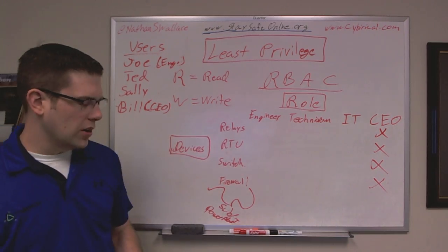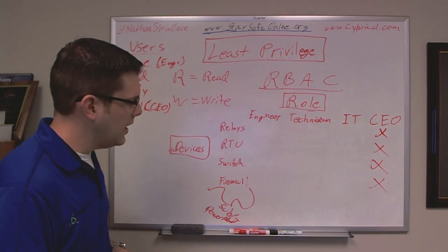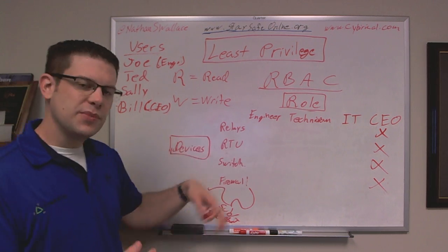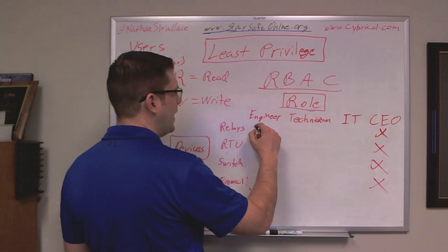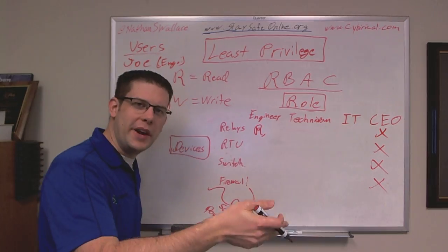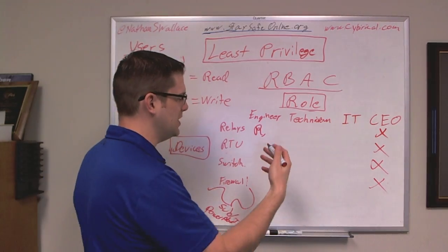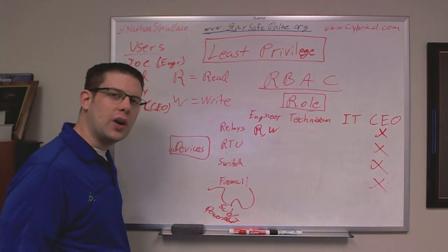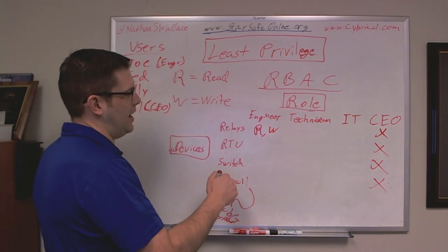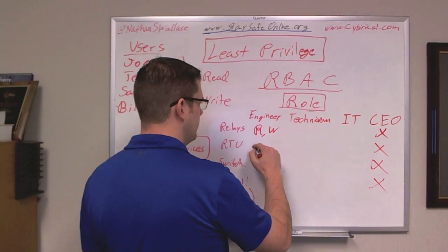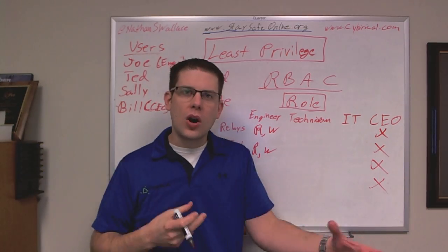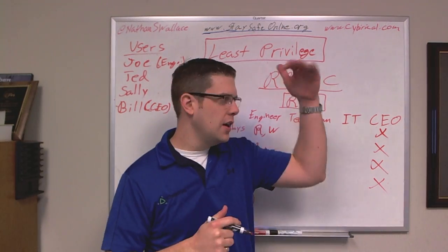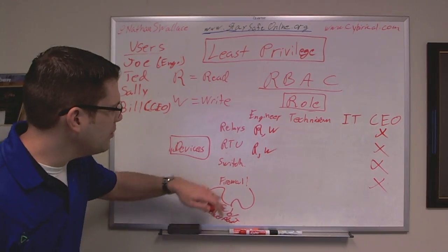And let's say, okay, during commissioning, testing, design, he needs to go in there and do some settings changes, some configuration changes. So yeah, he definitely needs read access, right? Because once he makes those changes, he has to read them back, as well as debugging, as well as write. So read and write for the relays and RTU, absolutely. He needs to be able to configure and test, to make sure that RTU and that relay can talk to each other, make sure those point maps are set and aligned properly.